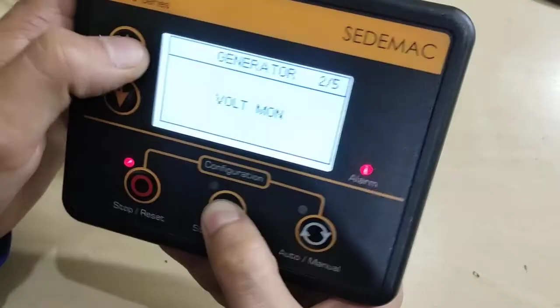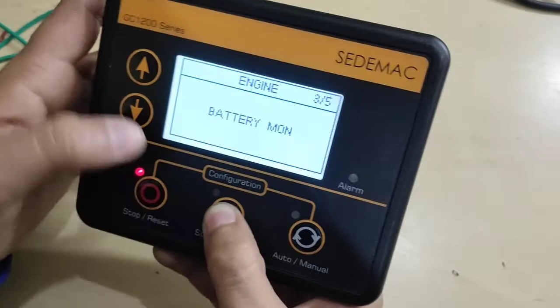You can select the voltage phase selection here. Alternator configuration, 4 poles, 3 phase system. You can select 1 phase here, or select 3 phase here. So this is for the generator, then mains, engine, crank disconnect. How many attempts will it take? These are the settings for cranking, and for speed monitoring and battery monitoring, what alarm will come when battery voltage is low, and after how much time this alarm will come. You can configure all this here.